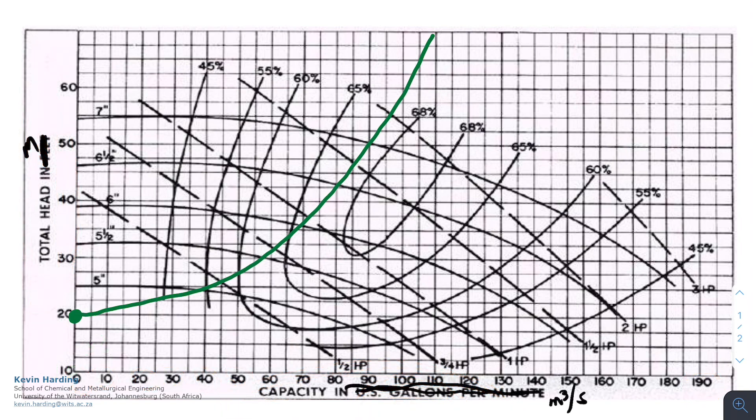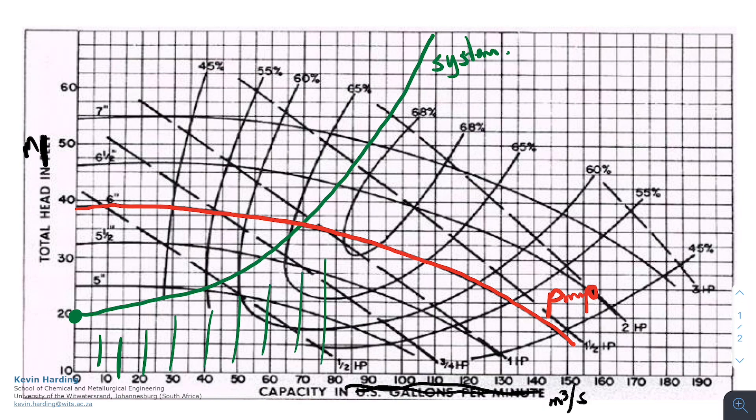What we now have is our system curve. So the green one is our system curve. This relates to what happens in our actual system and has nothing to do with the pump. We have, however, plotted it onto the pump curve. And if our pump curve is the one that I'm highlighting in red, we can now determine the operating point.